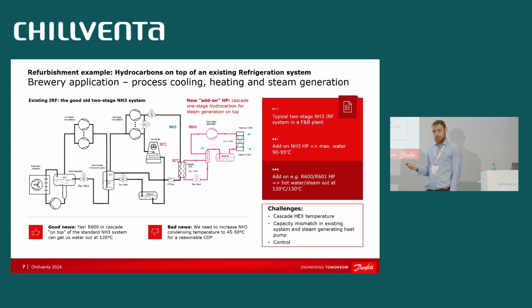Well, if you want to generate hot water up to 90, maybe on a good day 95 degrees centigrade, then ammonia is a fantastic heat pump to put on top of the existing system. It will have a very high COP. However, if you want to generate steam, then with minor exceptions, ammonia is not there yet. What is there and can be done is hydrocarbons. You can connect in a cascade after the high stage of the ammonia. And then just like the previous project, you can lift to 130 degrees condensing, generate steam at 2 bar. Logic is the same, but there are a bit more challenges. Among others is, okay, typically ammonia would condense in a refrigeration at 30-35 C, depending where in the world you are. But we need to elevate the condensing pressure to get to a proper source for the second stage, for the hydrocarbon.